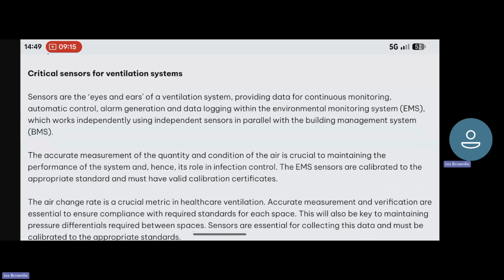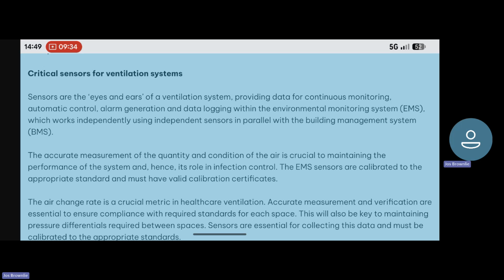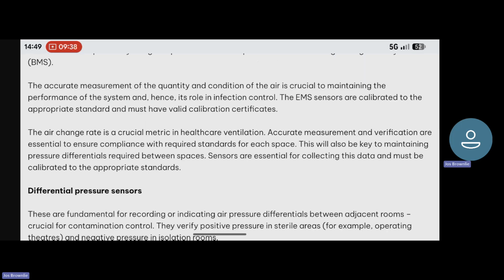Sensors are the eyes and ears of a ventilation system, providing data for continuous monitoring, automatic control, alarm generation, and data logging within the Environmental Monitoring System, or EMS, which works independently, using independent sensors in parallel with the Building Management System, or BMS. The accurate measurement of the quantity and condition of the air is crucial to maintaining the performance of the system and hence its role in infection control. The EMS sensors are calibrated to the appropriate standard and must have valid calibration certificates.